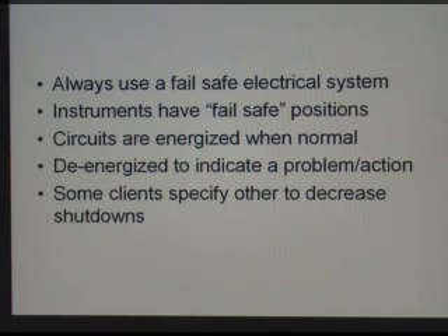Some clients actually do want to have it the other way. They want to have it so that you have an active signal to specify a shutdown, because that will decrease their accidental shutdowns because of wiring problems and broken instruments and things like that. But we would never do that initially. We'd have to have direction from a client to do that. That's a less safe system for the equipment.